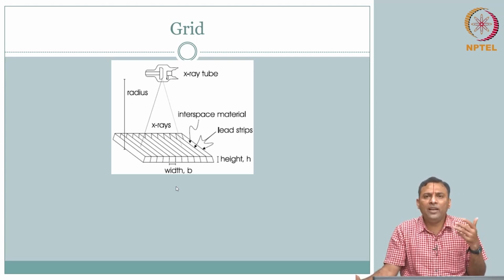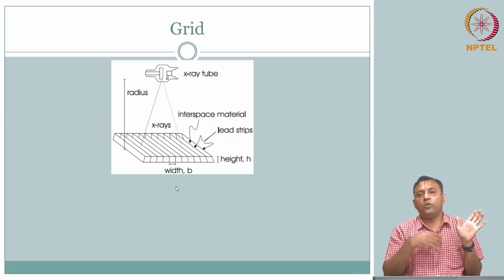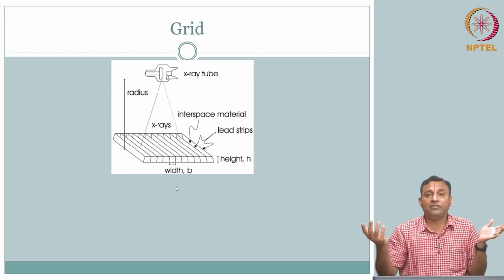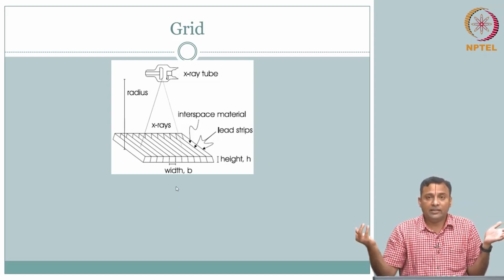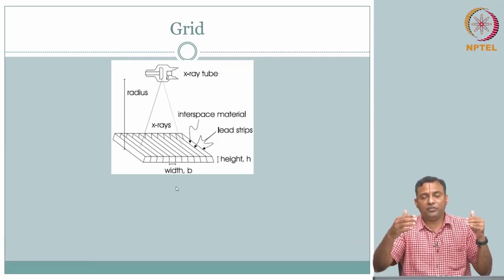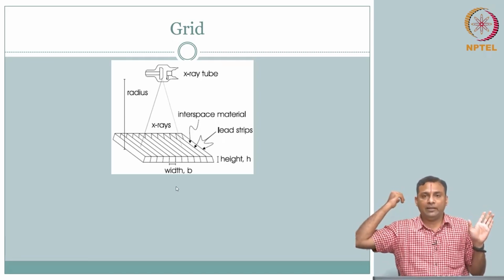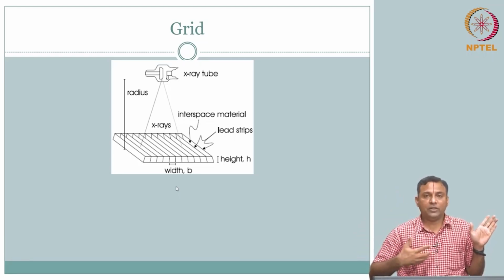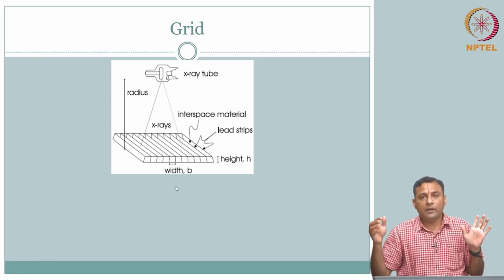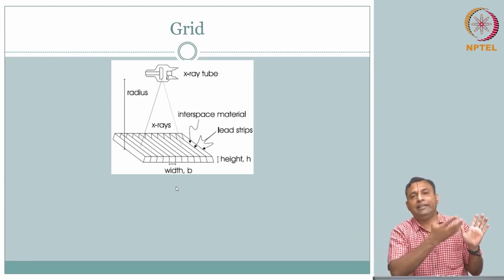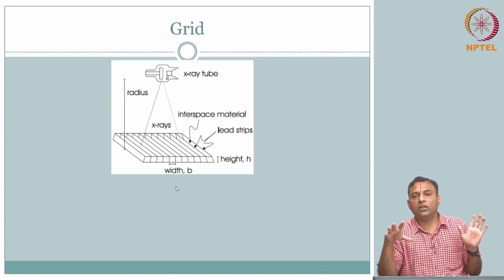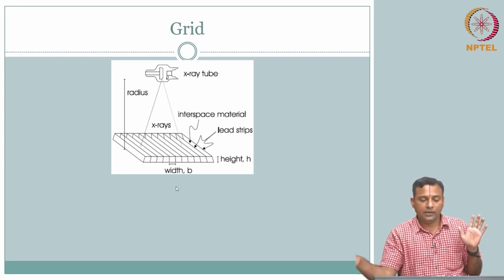So clearly it has gone through the patient. Now we are talking about coming outside the patient. It's Compton scattered and coming out. If it is Compton scattered and absorbed by the patient, we cannot do much. Our interest now is, assume we have sufficient signal that is coming out, which we want to detect so that we can form an image. How do we minimize the Compton scattering in the detector, so that the image quality is not compromised?